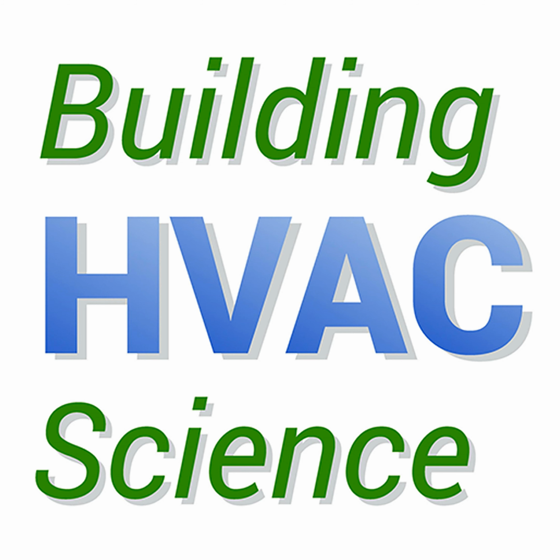That's a difference we see between a hydronic system and a refrigerant based system. The hydronic system has a lot more variable capability. With hydronic, you can also have underfloor heating in a single system alongside cooling. With underfloor heating, we can supply a temperature of 85 degrees and still have a very comfortable warm home, with much higher efficiency.